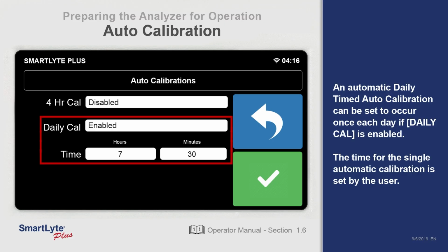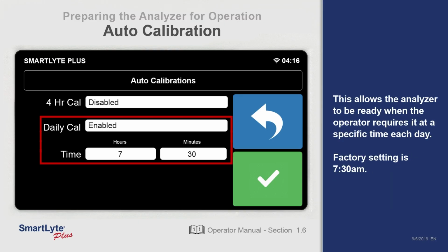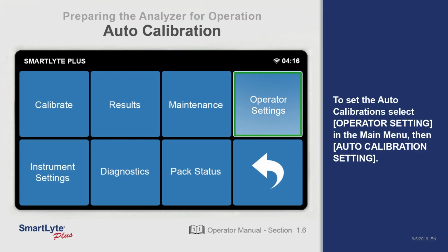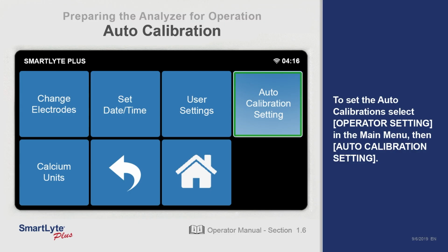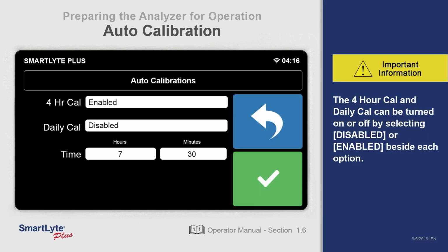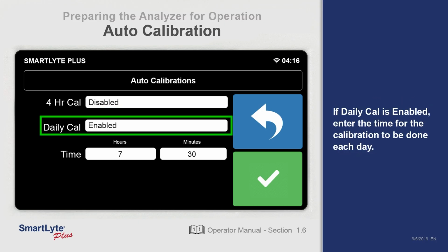An automatic daily timed auto calibration can be set to occur once each day if daily calibration is enabled. The time for the single automatic calibration is set by the user. This allows the analyzer to be ready when the operator requires it at a specific time each day. The factory setting is 7:30 a.m. To set the auto calibration, select Operator Setting in the main menu. Then select Auto Calibration Setting. The 4-hour calibration can be turned off or on by selecting Disabled or Enabled. If enabled, enter the time for the calibration to be done each day.